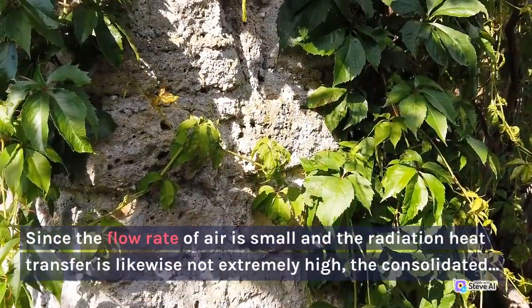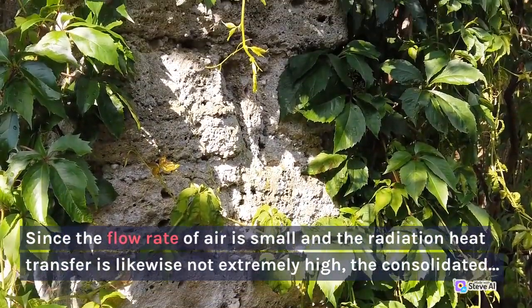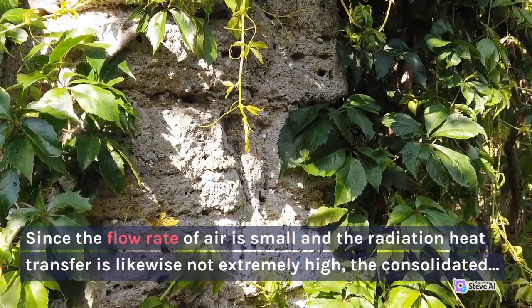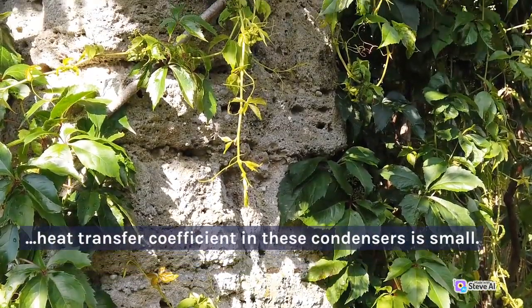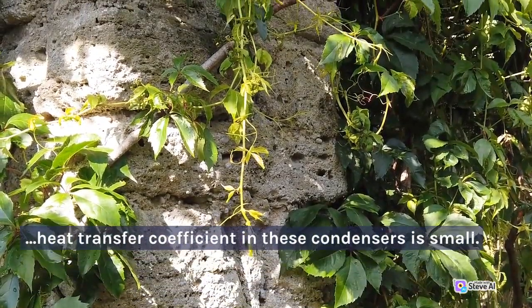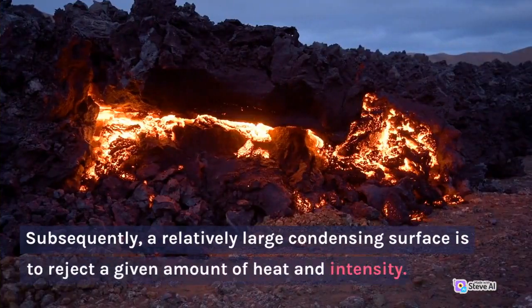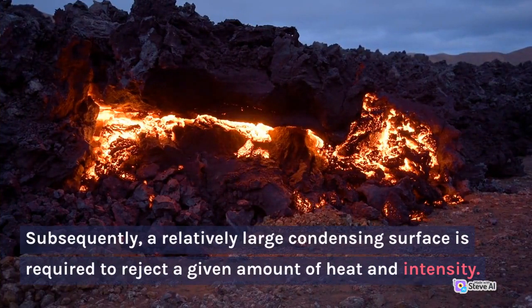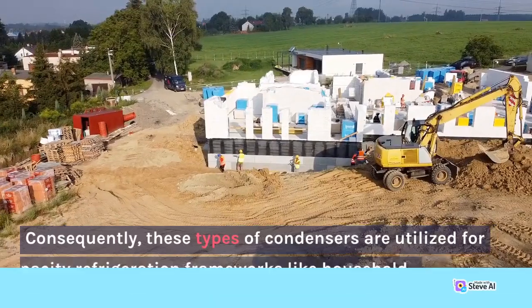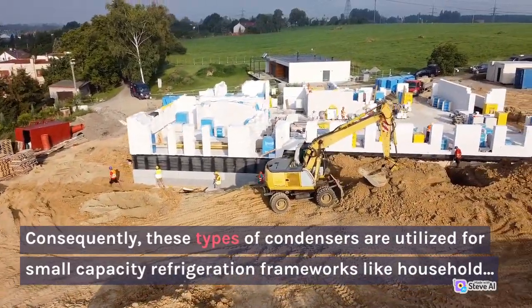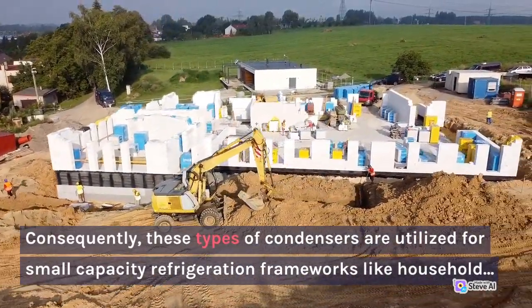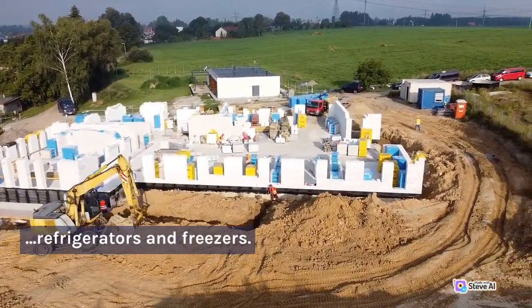Since the flow rate of air is small and the radiation heat transfer is likewise not very high, the combined heat transfer coefficient in these condensers is small. Subsequently, a relatively large condensing surface is required to reject a given amount of heat and intensity. Consequently, these types of condensers are used for small-capacity refrigeration systems like household refrigerators and freezers.